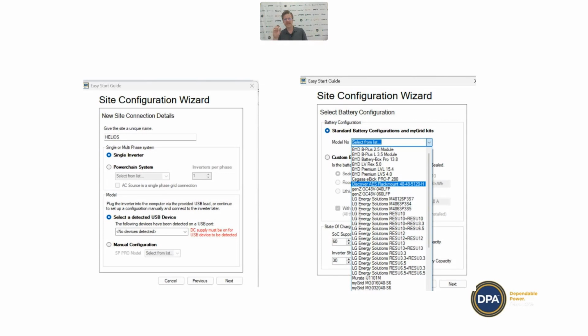The reason for that is because the BMS is the same - it actually has the same firmware. Jeff, my colleague in the tech department, accidentally wrote the Helios firmware to one of the rack mount batteries, and we all thought that was going to ruin it, but it didn't. It worked perfectly fine. I found out from Discover afterward that it's actually exactly the same firmware, which is why all the charge settings and everything are identical. It just enables different parts depending on the system, but the system itself is identical, so we can use those same values.